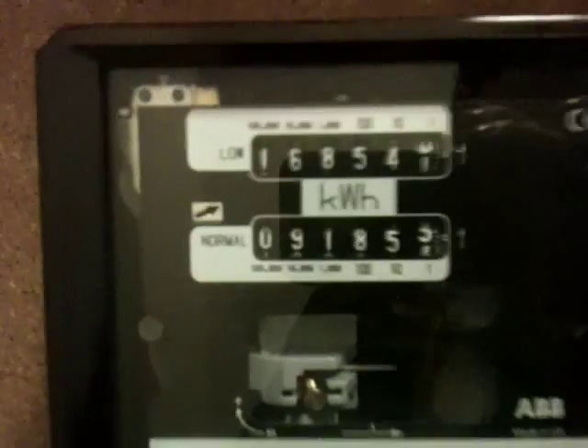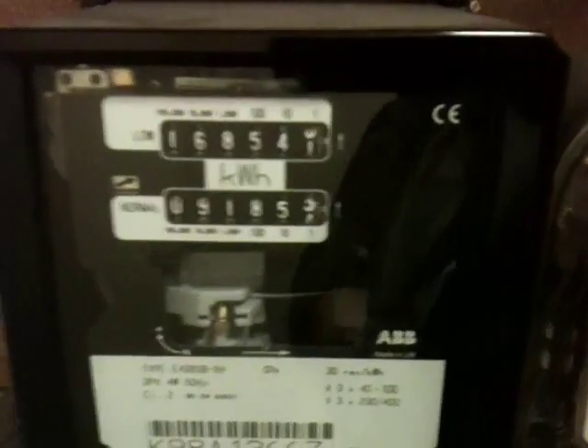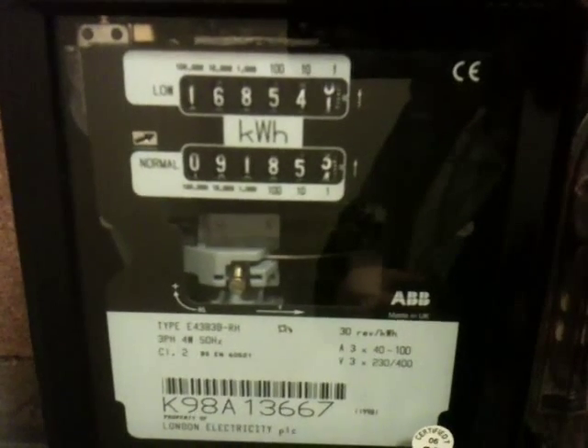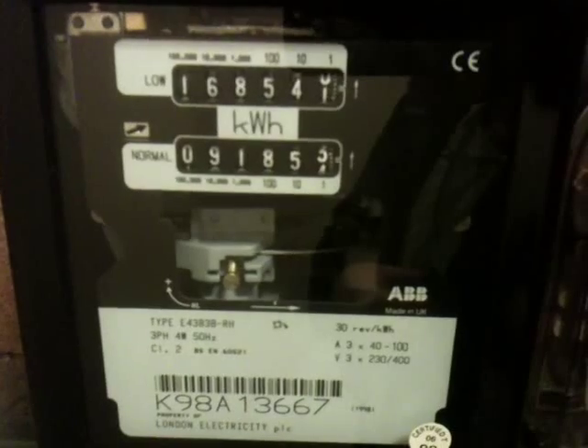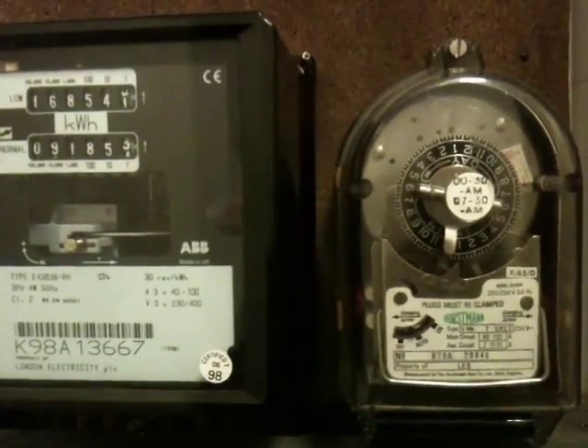Here we have the three-phase four-wire meter — this is an ABB meter, two-rate as you can see — and it's a three-phase whole current meter, 40 to 100 amps, 230 and 400 volt, three-phase supply, 50 hertz, and it's a whole current meter. The meter constant in this case is 30 revolutions per kilowatt hour, because it's designed for heavy load.